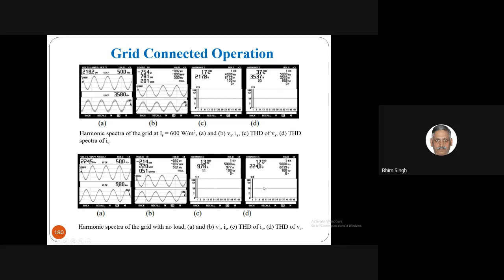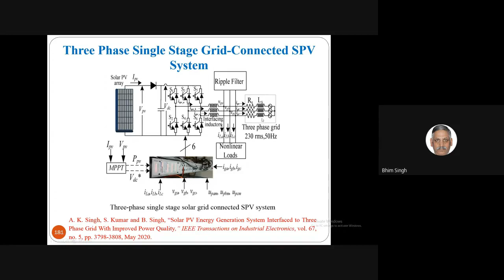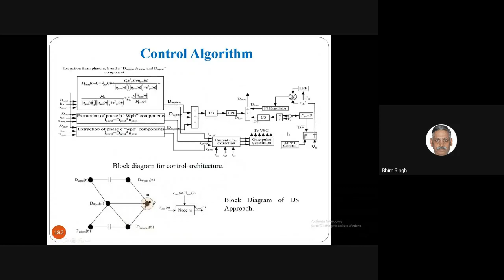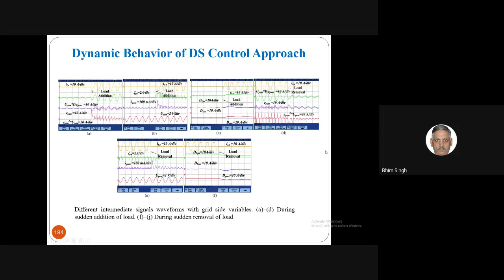Then of course we extended the work to a 3-phase single stage system, taking care of full utilization of the inverter for 24 hours, compensating the local load and feeding sinusoidal current at unity power factor to the grid, even when solar insolation or load changes. So we modify the control, and we use this kind of intelligent control algorithm, a distributed dispatch control algorithm. You can clearly see when load addition happens, how the control mode automatically takes care of that.